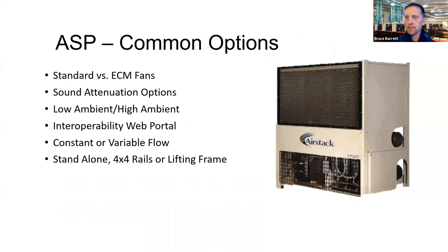Common options we can do, again, standard fans, ECM fans. We can mount a number of low sound attenuation options on these. Again, our aforementioned low ambient and some high ambient capabilities. We do a lot of desert locations with our embassy work over in the Middle East, all the way up to 120 high ambient conditions. We offer a web portal. It can be constant flow. It can be variable flow. It can be standalone modules. We can mount them on rails or lifting frame.